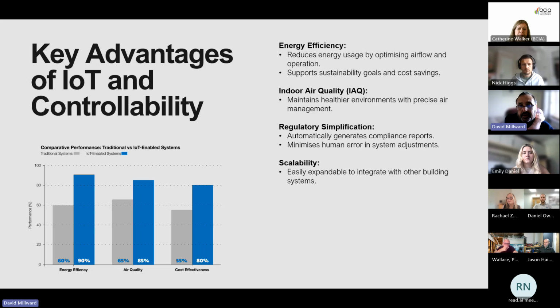The benefits are quite clear. There's a number of studies. The graph I've got, the bar chart I'm showing here, is very generic. It's based on really, if we provide greatly improved efficient components within ventilation products such as EC motors, high efficiency motors that allow us to reduce energy just purely in the fact that we're using more efficient machines, but also on that the controllability of that machine only ventilating at the times we need to ventilate. If we reduce the fan speed by 5%, we'll typically get on average a 20% saving in actual power usage. So speed control is a massive part.